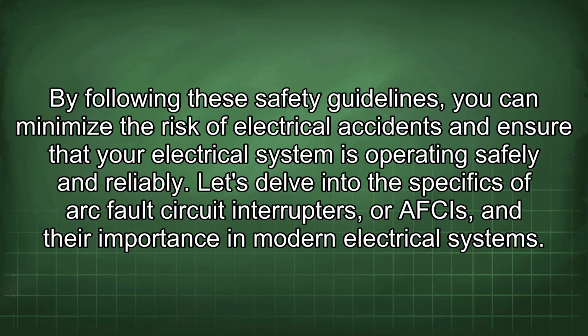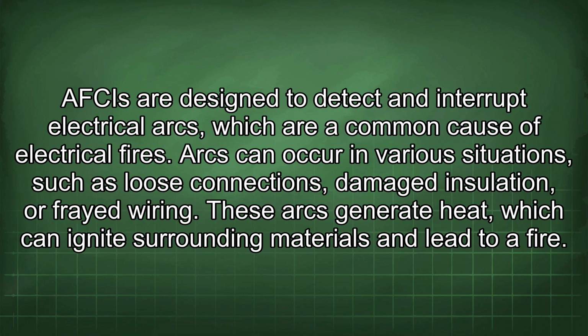Let's delve into the specifics of arc fault circuit interrupters, or AFCIs, and their importance in modern electrical systems. AFCIs are designed to detect and interrupt electrical arcs, which are a common cause of electrical fires. Arcs can occur in various situations, such as loose connections, damaged insulation, or frayed wiring. These arcs generate heat, which can ignite surrounding materials and lead to a fire.